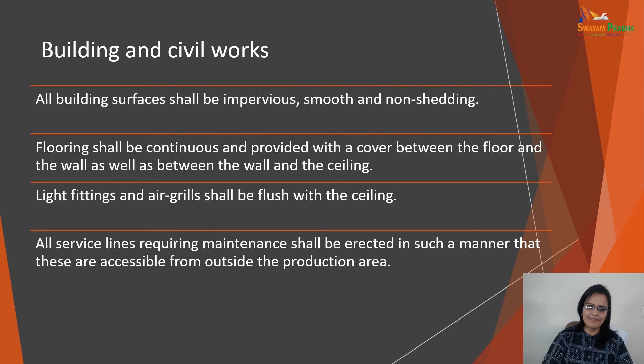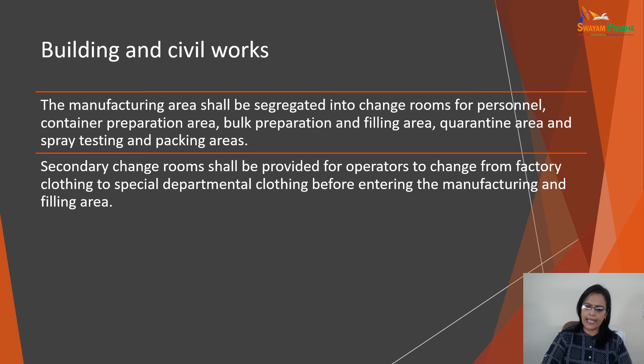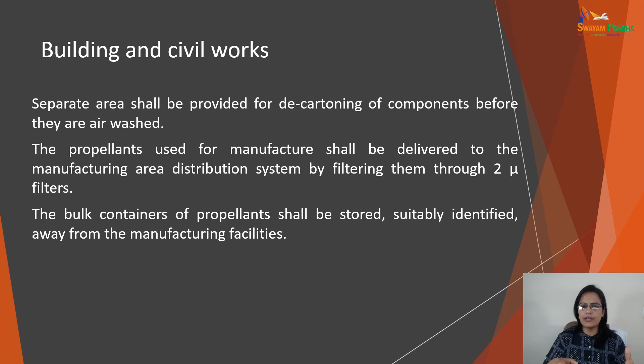Next, the manufacturing area shall be segregated into the change room for the persons, container preparation area, bulk preparation area, filling area, quarantine area. These areas should be separate from each other. A secondary change room shall be provided for the operators to change from factory clothing to the special departmental clothing before entry into the manufacturing and filling area. A separate area shall be provided for decartoning of components before they are air washed. The propellants used for manufacturing shall be delivered to the manufacturing area distribution system by filtering them through 2 micron filters. Now that was about the layout, the requirements of the building and civil work.